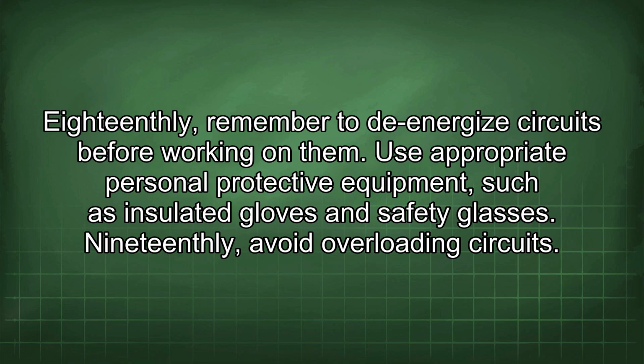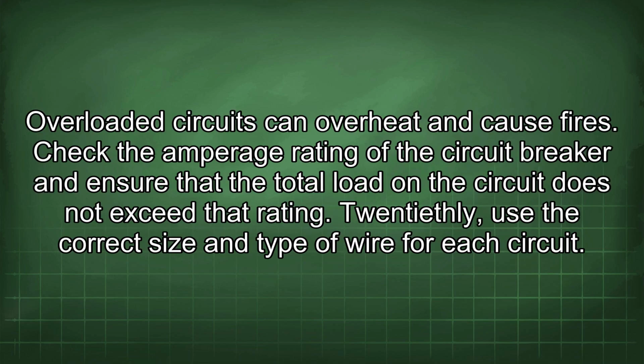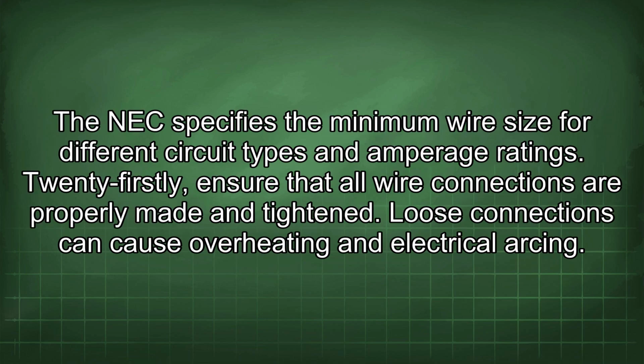19thly, avoid overloading circuits. Overloaded circuits can overheat and cause fires. Check the amperage rating of the circuit breaker and ensure that the total load on the circuit does not exceed that rating. 20thly, use the correct size and type of wire for each circuit. The NEC specifies the minimum wire size for different circuit types and amperage ratings. 21stly, ensure that all wire connections are properly made and tightened. Loose connections can cause overheating and electrical arcing.